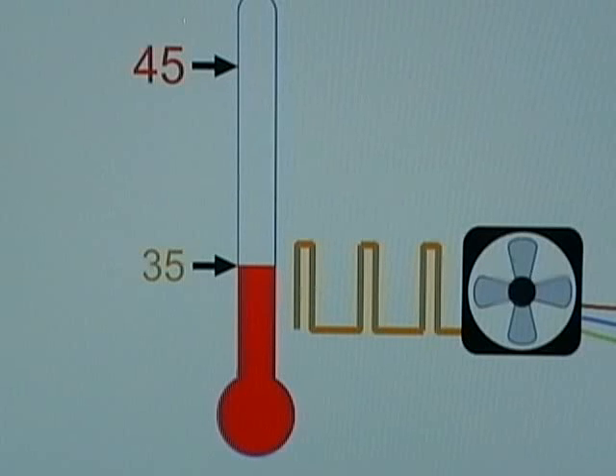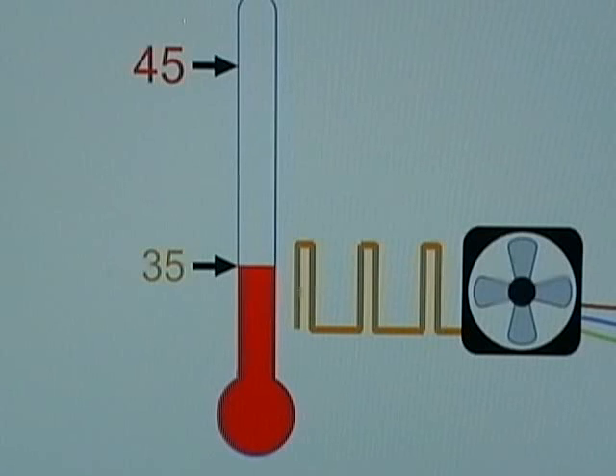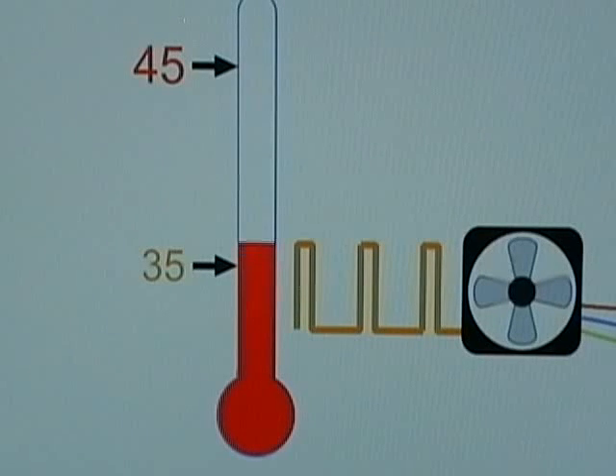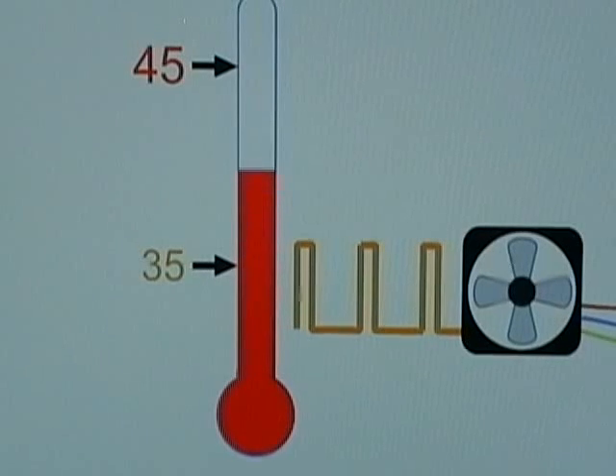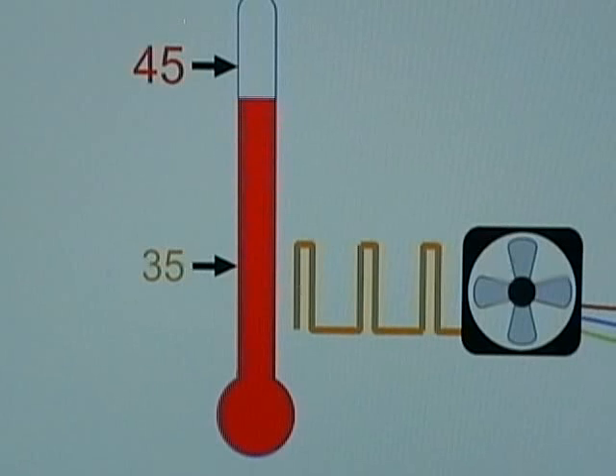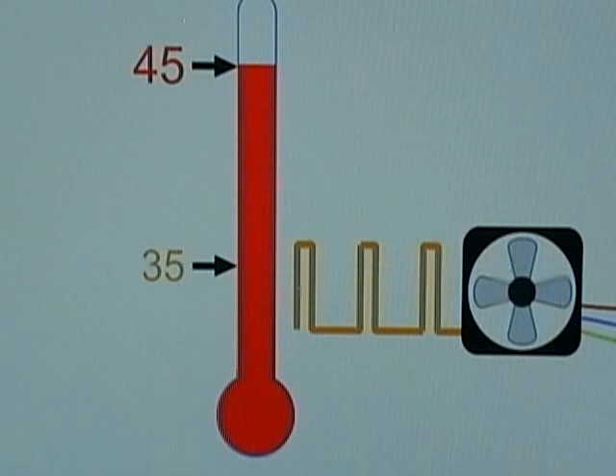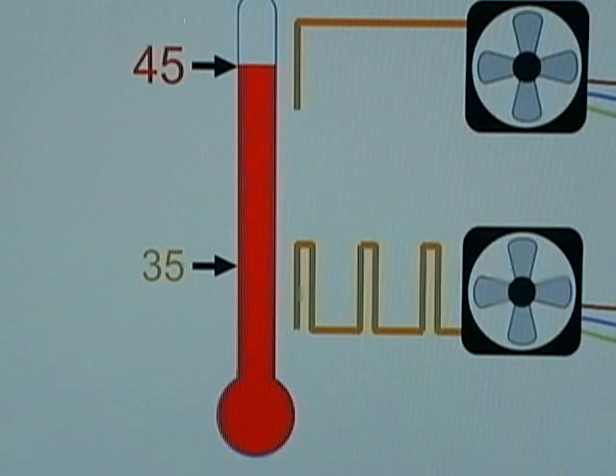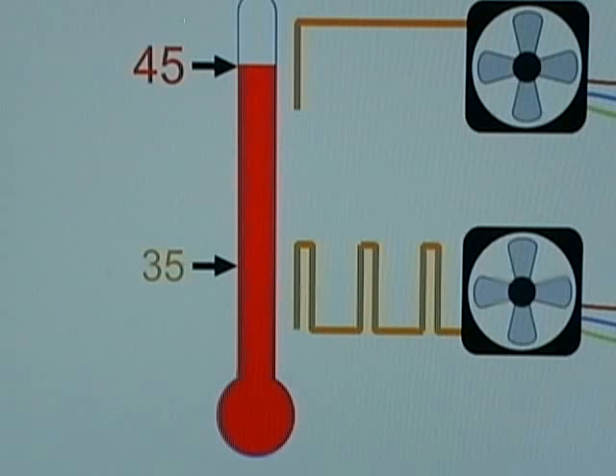The second set point is the high temperature set point. This is supposed to be a critical value, where the device needs urgently more air for cooling. When the temperature at the NTC sensor goes over the set point, the fan will be powered with constant current causing it to rotate at full speed.